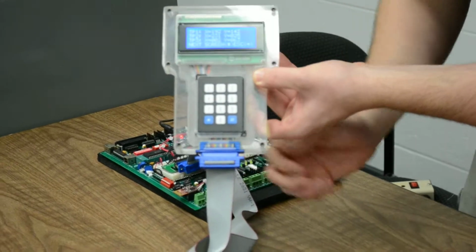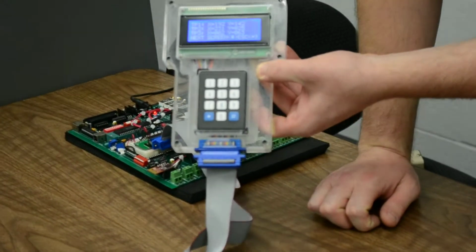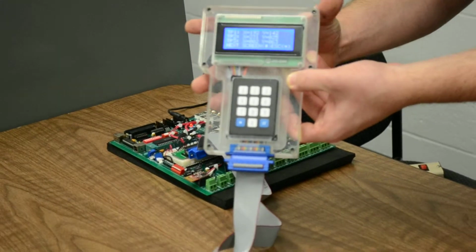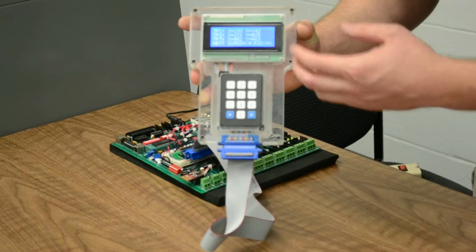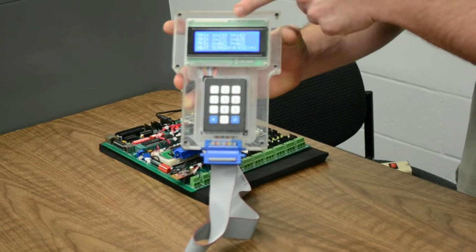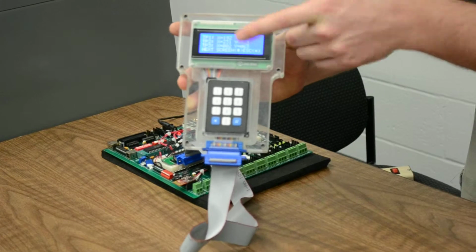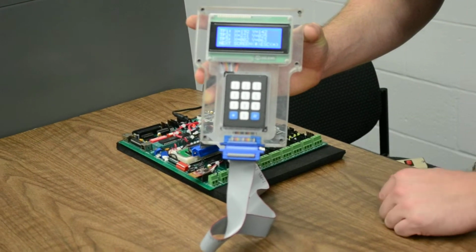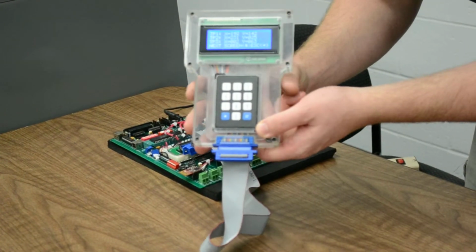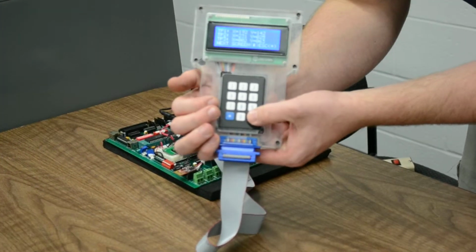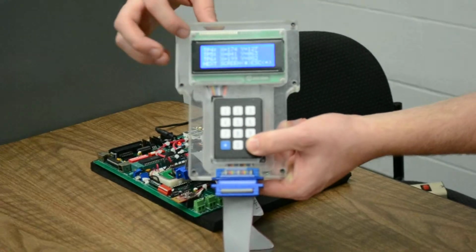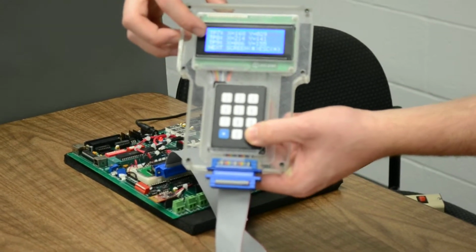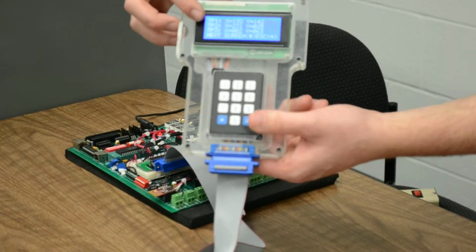Well, for viewing teach points, in the manufacturing world, anytime you have a robotic system or anything that's automated, you have a way of viewing where your actual teach points go, what the actual settings are. Same concept here. We have the X and Y coordinate. For teach point 1, we have like 192 steps, and for the Y coordinate, 142 steps for the next one. And if you'd like to continue on seeing the rest of the teach points, you hit the pound key for next page, and it'll toggle to the next page. Teach point 4, 5, and 6, all the way up to 9. And if you keep toggling, it'll go back to the original page.